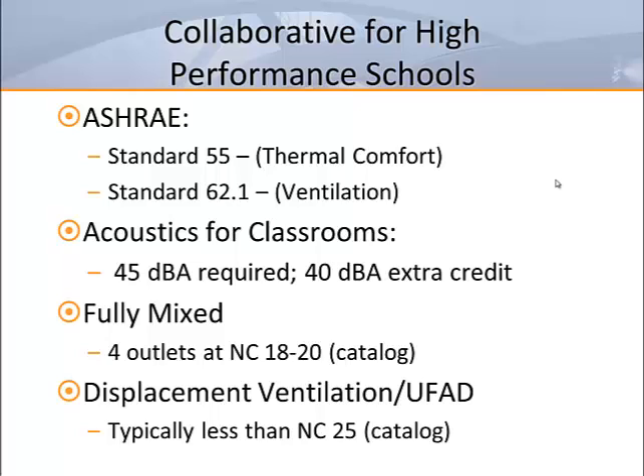Let's examine the leading sources for guidance for high-quality designs for schools. CHPS recommends a design which meets or exceeds the thermal comfort requirements of ASHRAE Standard 55 and the ventilation IAQ requirements of ASHRAE Standard 62.1. The recommended acoustic requirement for classrooms is 45 dBA, with extra credit for 40 dBA, and the ultimate goal of reaching the ANSI recommendation of 35 dBA.